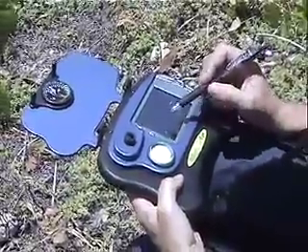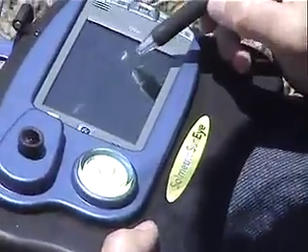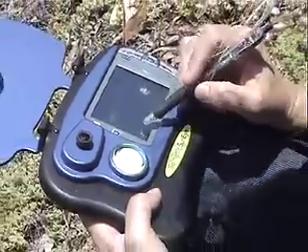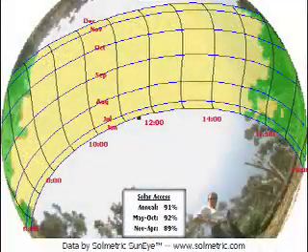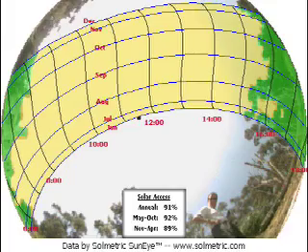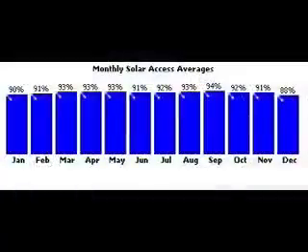This is a Solmetric SunEye, which actually measures the incident radiation. It figures out what it's going to do over the course of the year. You're going to have a little shading in the morning before 9 o'clock and then after around 3 o'clock. So you have 6 hours of full sun, and your average is 90%.